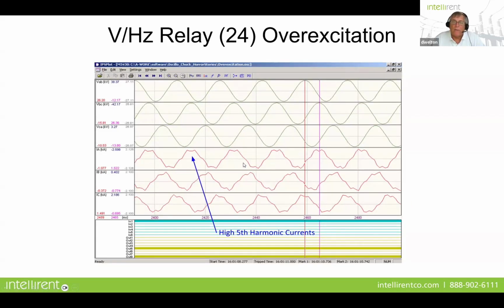So what we see when we have a volts per hertz condition is a lot of fifth harmonic component in the waveform of the current. And this is a good thing to have happen, and I want to explain the difference between fifth harmonic restraint and volts per hertz protection. When you have a volts per hertz protection element enabled for the transformer, you also want to enable a fifth harmonic restraint, because you may have enough volts per hertz condition to set off the differential without actually having enough volts per hertz to trip that protective element. So the smallest inclusion of a volts per hertz condition will generate this fifth harmonic. That's why we need to enable the fifth harmonic restraint, so we don't trip from just a quick overexcitation event that's not going to do any damage. So that's the difference between fifth harmonic current and volts per hertz protection. A lot of people get confused as to what the fifth harmonic current or that fifth harmonic restraint is there for.